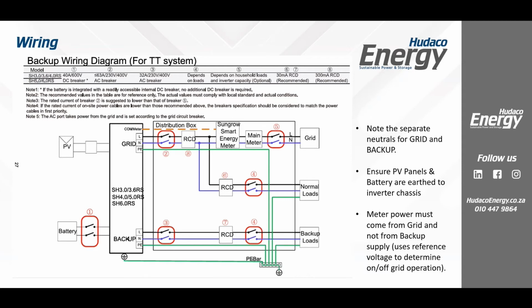Okay, if they don't, normally the very first thing you see is lights start to flicker, especially during transfer times, and not all normal lights, but especially if you've got LEDs. And the easiest way to tell is it's LEDs with poor drivers that'll start flickering first, and that's a really great way to say, oh well, maybe the first thing I must do is just go make sure my neutrals are separate. Okay, if we don't do that, we can end up thinking we've got a problem on site or with the hardware. The second thing, which we've already discussed, is please ensure that the panels and the batteries are earthed to the chassis.